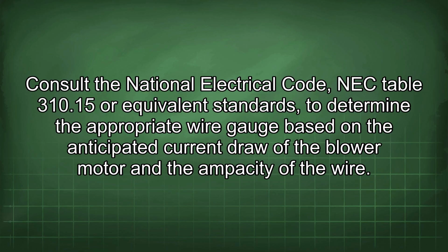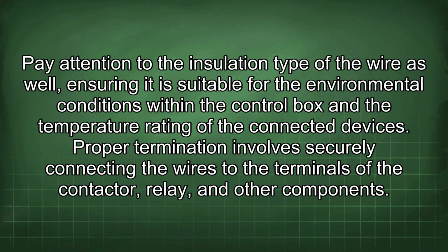Consult the National Electrical Code, NEC Table 310.15 or equivalent standards to determine the appropriate wire gauge based on the anticipated current draw of the blower motor and the ampacity of the wire. Pay attention to the insulation type of the wire as well, ensuring it is suitable for the environmental conditions within the control box and the temperature rating of the connected devices.